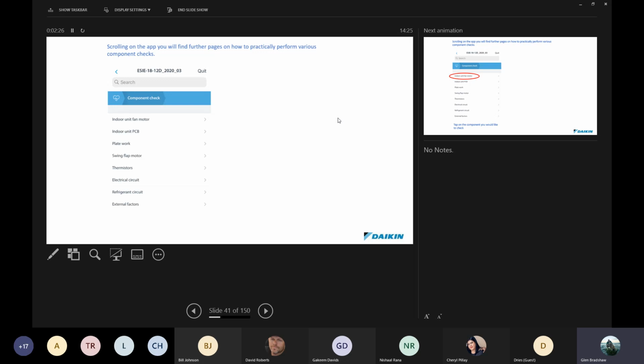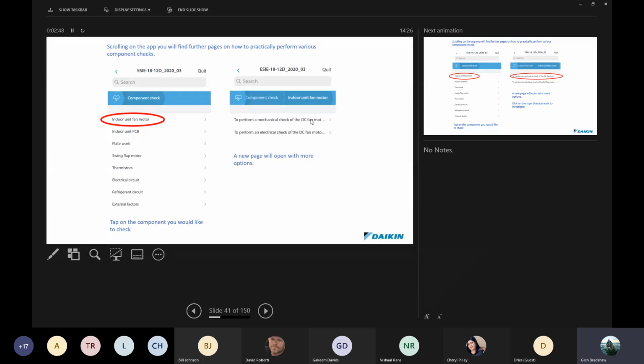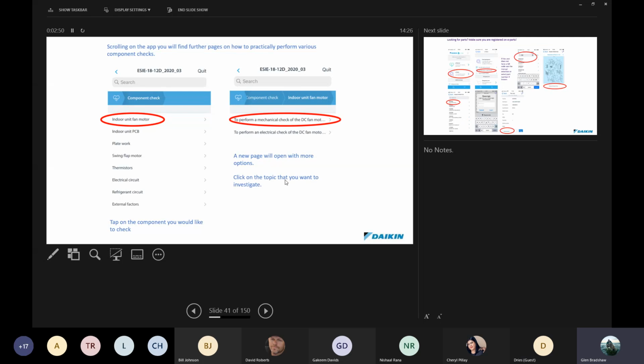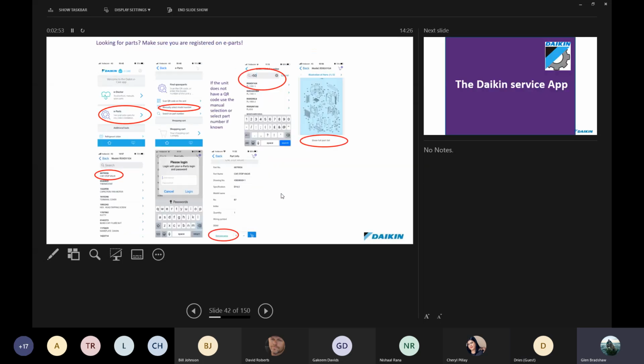All right. Other component checks are available, and these are for indoor unit fan motors, the indoor unit PC board, plate work, the swing flap motor, thermistors, electrical circuit, refrigerant circuit, and external factors. If you chose an indoor fan motor, for instance, and you tapped on that, then it would bring you up with the checks that you would need to perform. Basically there. And then it can also link you to eParts if you're registered on there. That's just another application, but if you're not registered, don't worry too much.